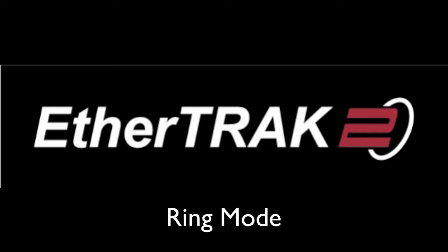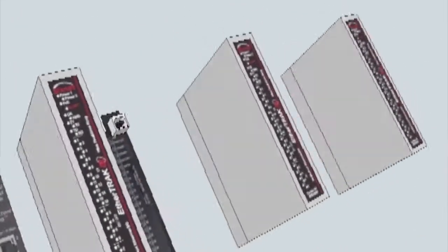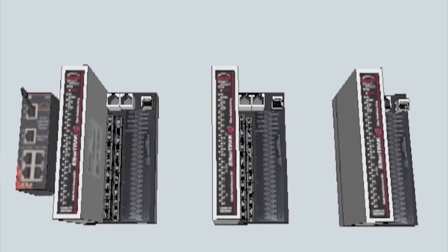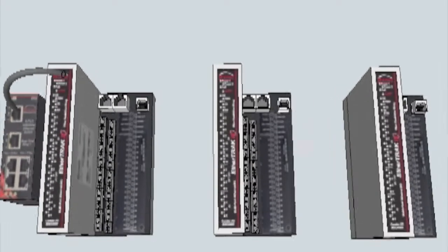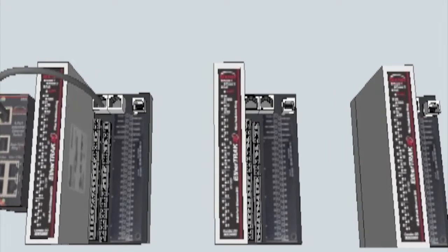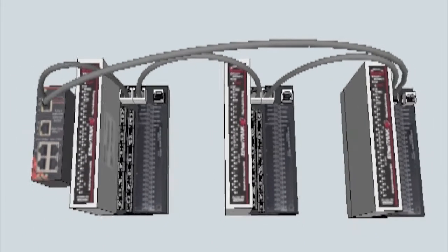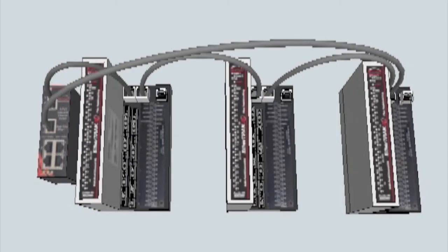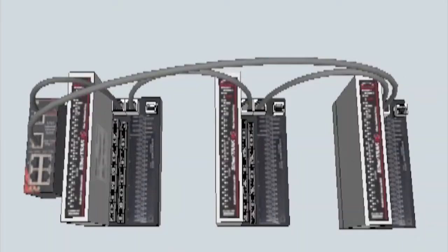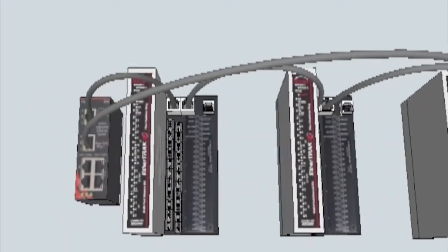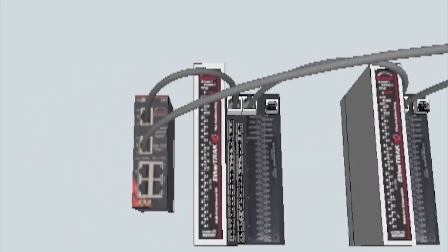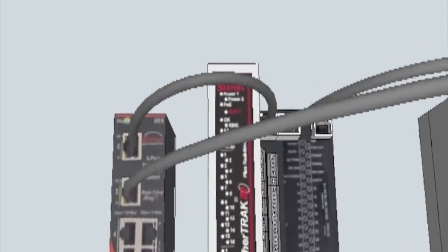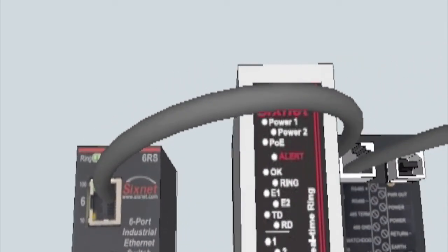The first option is ring configuration. This option offers the best in performance and redundancy. It utilizes the switch built into the EtherTRAK 2 with Sixnet's proprietary ring switch algorithm. The redundant ring architecture means that any one network link can be disconnected or cut and the network will still keep running. The fast ring protocol makes recovery effortless and as fast as 5 milliseconds per hop on the network.